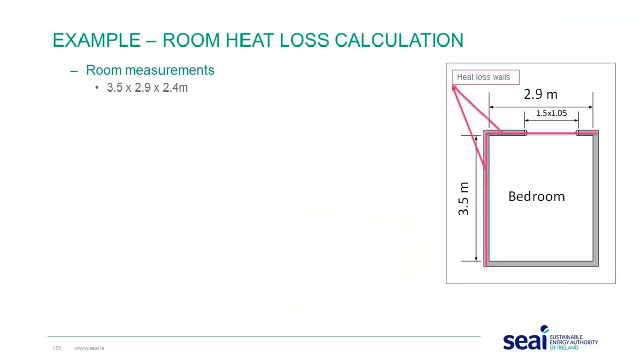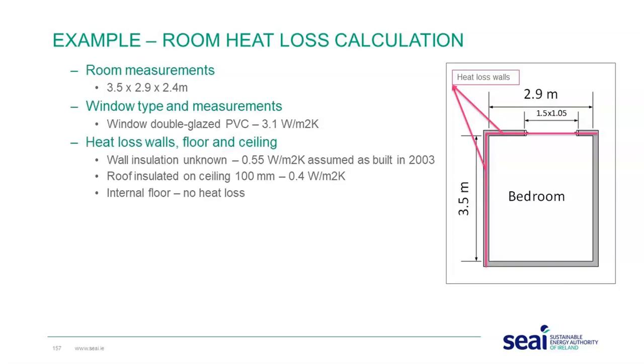Now, the next thing we need to do is look at the room. As I mentioned earlier, we need to do room by room calculations. So I have an example here of a bedroom. We take the bedroom and we need to take certain information. So we do our sketch, we take our room measurements, and we take the information, so what window type and the dimensions of the windows. We need to look at the fabric, so the heat loss for the walls, the floor, and the ceiling. We need to look at the rad size. So in the example previously, I've taken the same radiator for consistency.